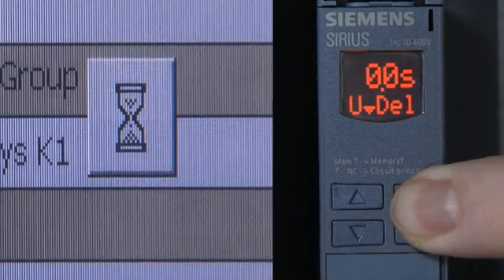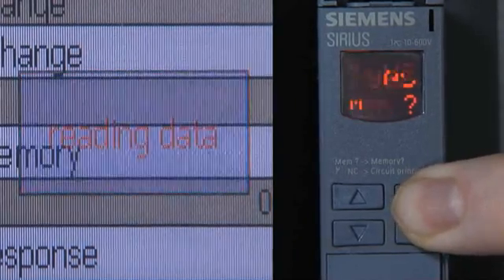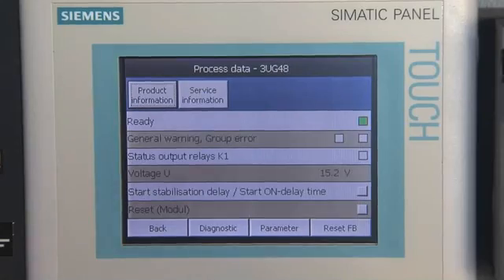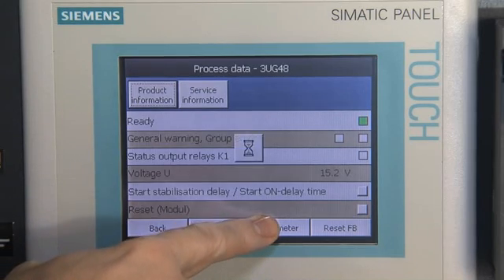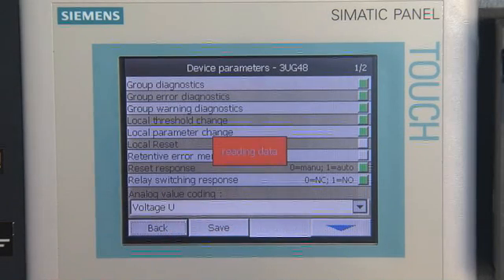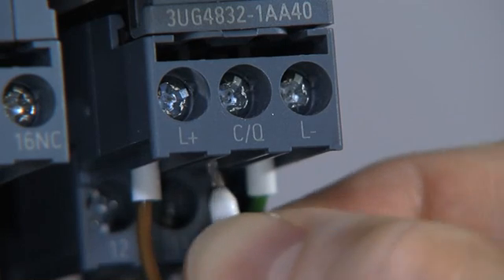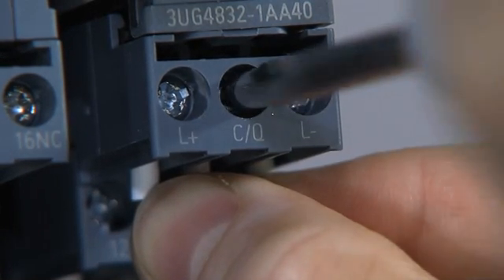Thanks to bidirectional communication, all the commissioning parameters are exchanged between relay and controller in addition to the measured values. Parameter assignment and first commissioning can thus be carried out with PC support, and a replaced monitoring relay can be parameterized automatically by the controller.